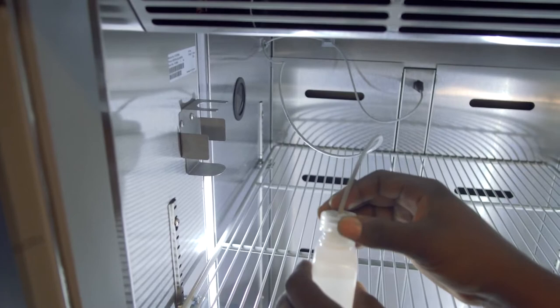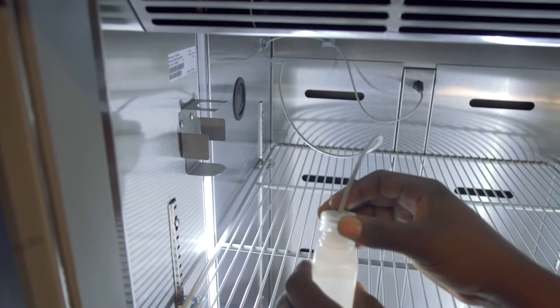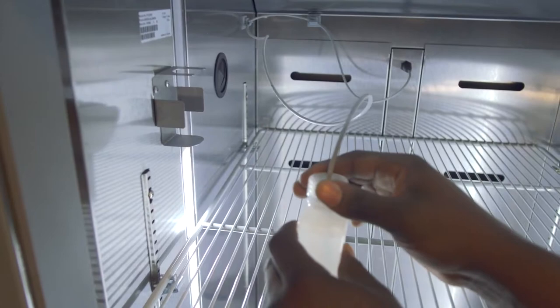Install the glycerin bottle within the unit. Insert the probe into the solution and re-tighten the bottle lid. Leave the remaining glycerin in the 16-ounce bottle with the end user.